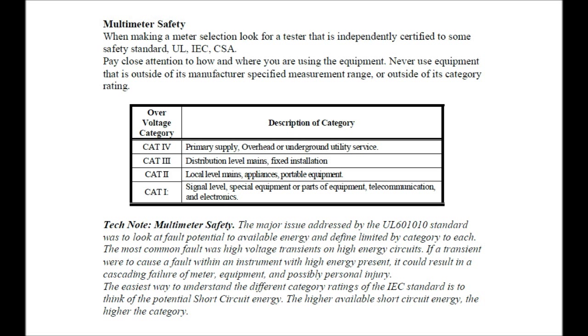Multimeter safety: the major issue addressed by the UL 61010 standard was to look at fault potential relative to available energy and define limits by category. The most common fault was high voltage transients on high energy circuits. If a transient were to cause a fault within an instrument with high energy present, it can result in a cascading failure of meter equipment and possible personal injury.